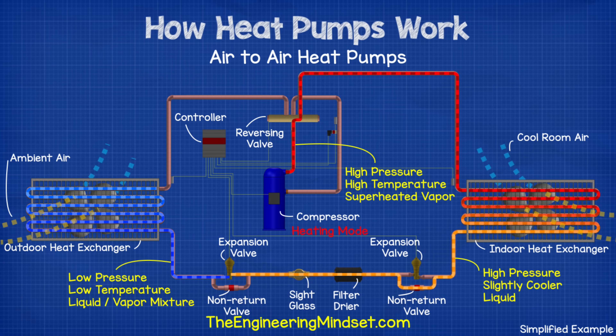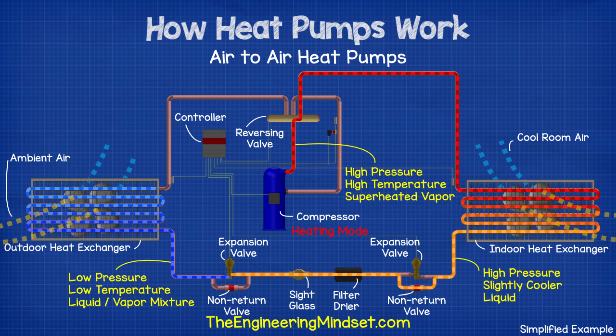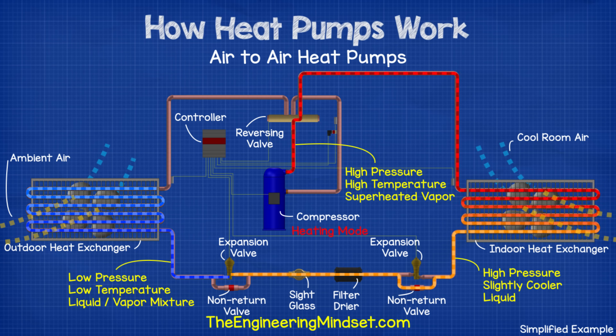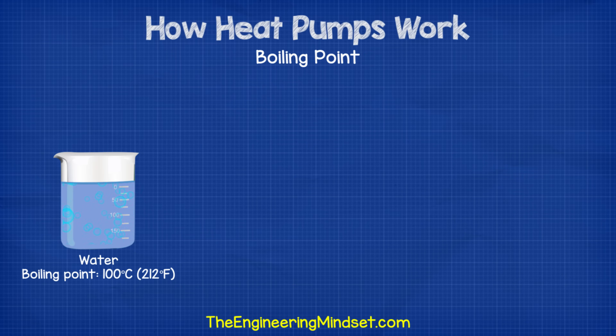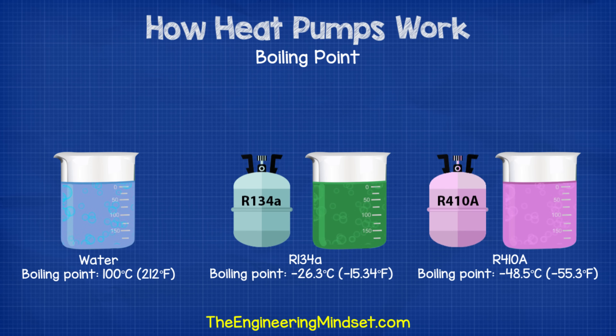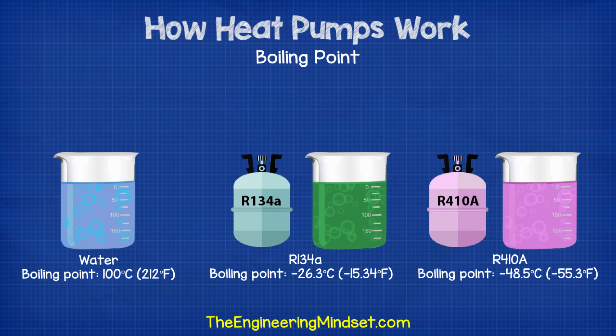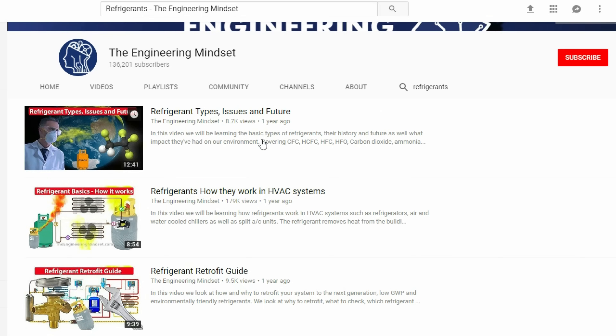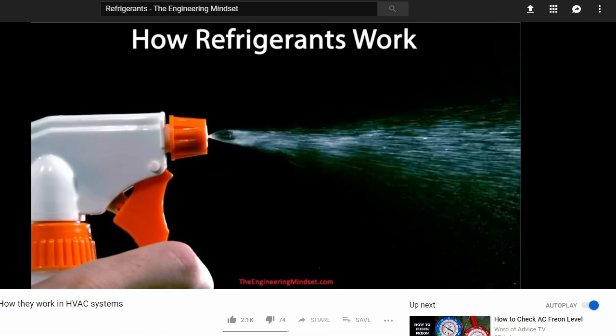The refrigerant then heads to the outdoor heat exchanger, where a fan is blowing outside ambient air over the coil and adding heat to the cold refrigerant. The refrigerant boils at a very low temperature and as it boils, it will carry away the thermal energy. For example, we know that water carries thermal energy away as steam when it boils at 100 degrees Celsius or 212 degrees Fahrenheit. If we look at some common heat pump refrigerants: R134A has a boiling point of minus 26.3 degrees Celsius or minus 15.34 degrees Fahrenheit, and R410A has a boiling point of minus 48.5 degrees Celsius or minus 55.3 degrees Fahrenheit. So it's very easy to extract thermal energy even at very low outdoor temperatures. We've covered how refrigerants work also in a previous video — links can be found in the video description below.